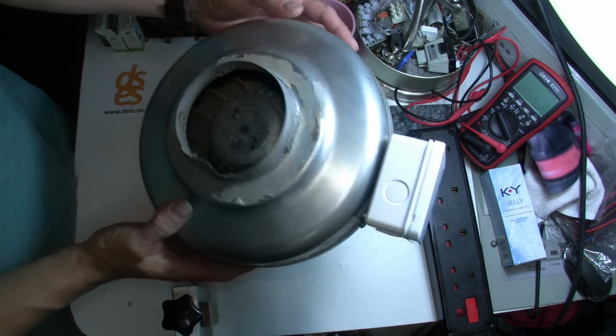When I charge the capacitor, I'm applying a positive voltage from the Robin's point of view. When the capacitor discharges, it shows a negative voltage on the display. That is, of course, because the DC voltage is now pointing in the opposite direction. Previously, the tester was putting out plus 280 volts into a capacitor at 0 volts. Now it's the other way around, with the capacitor putting out plus 280 volts back into the Robin. And because it's coming back in the opposite direction to how it went out, the Robin shows it as a negative voltage. The Robin's at 0 volts, the capacitor is 280 volts below it from the Robin's 0 volt perspective.